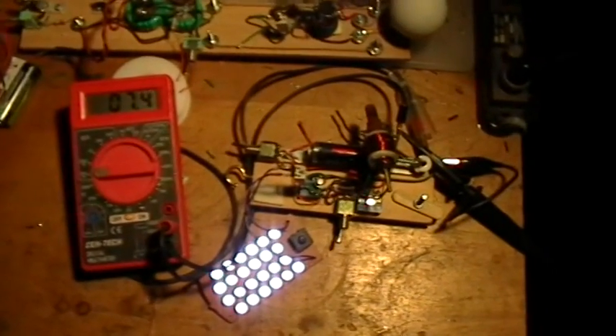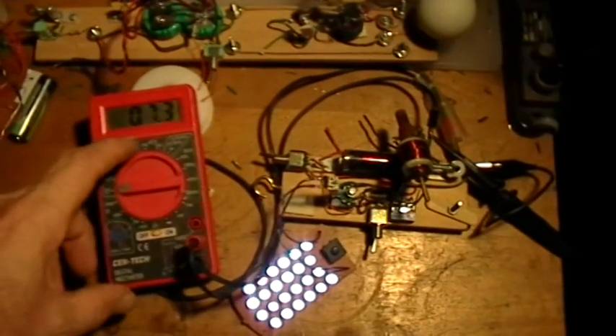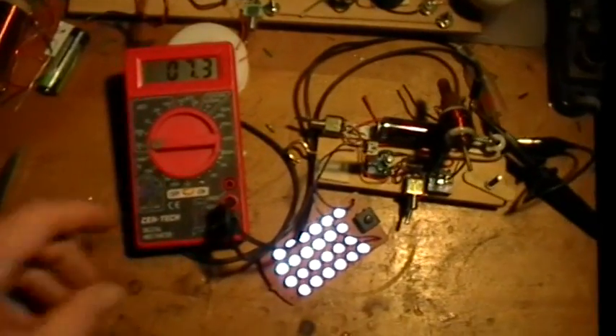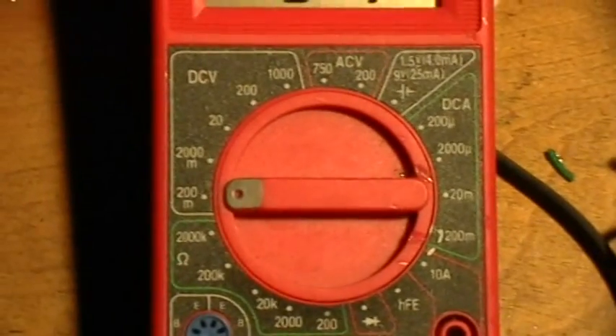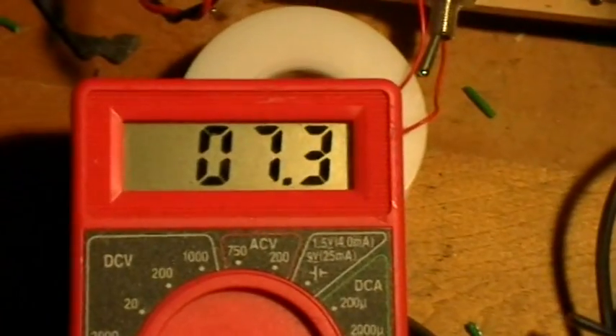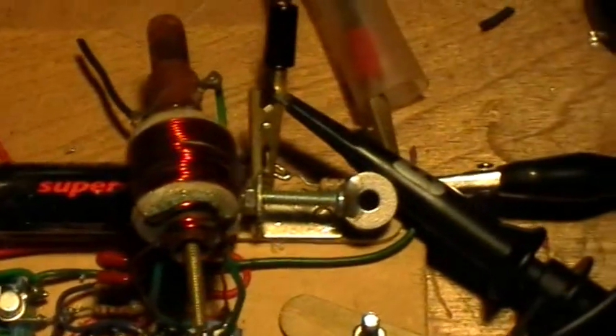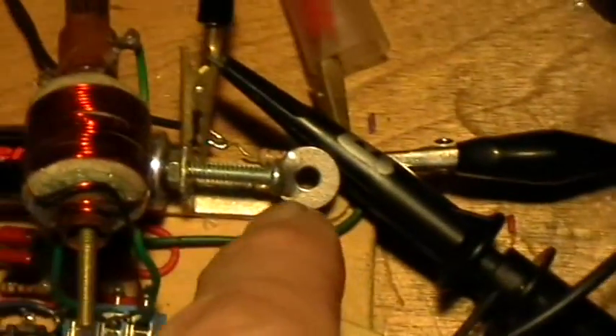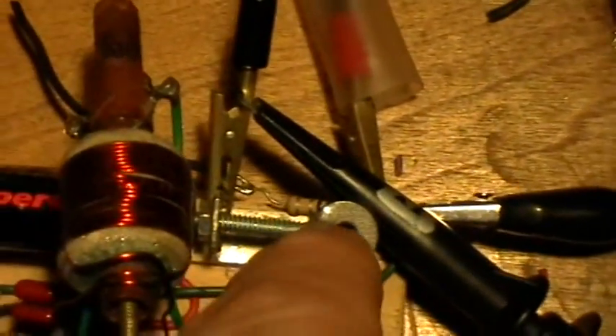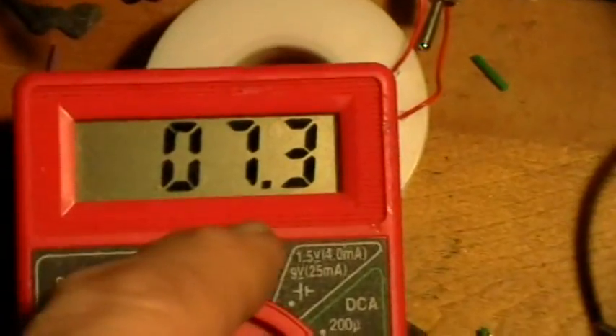Okay, here's the setup. This is a calibration of this meter. Right now I have it on the 200 millivolt setting, and it's reading 7.4 millivolts, and that's the voltage drop across the 1-ohm current viewing resistor that you can see down in there. So that translates to 7.3 milliamps current.